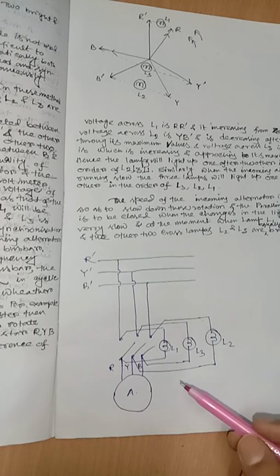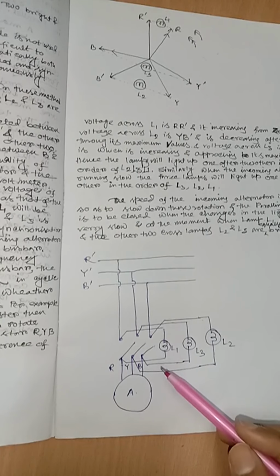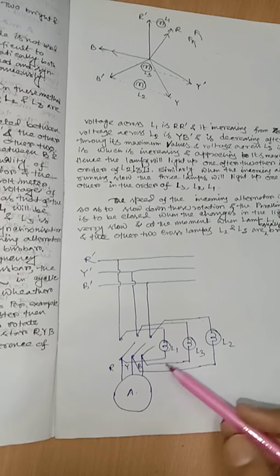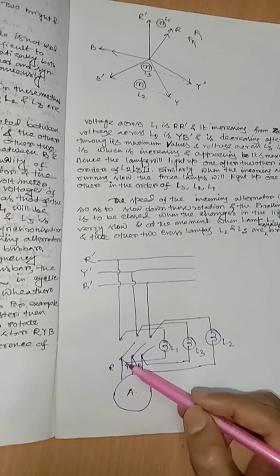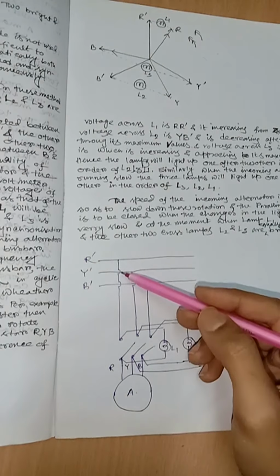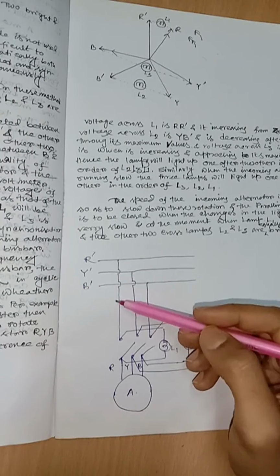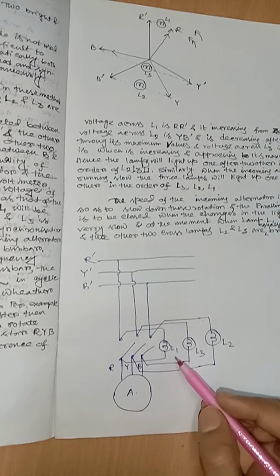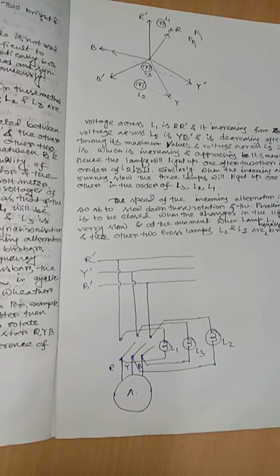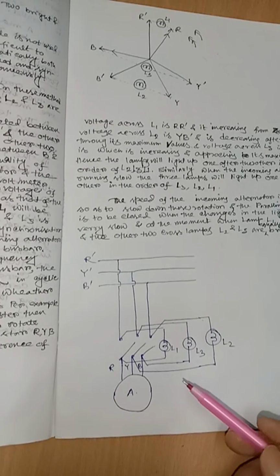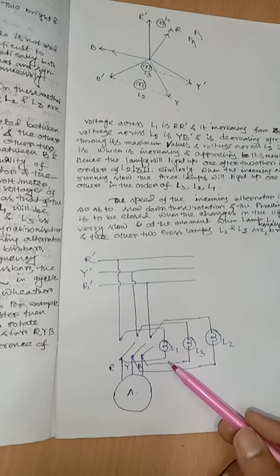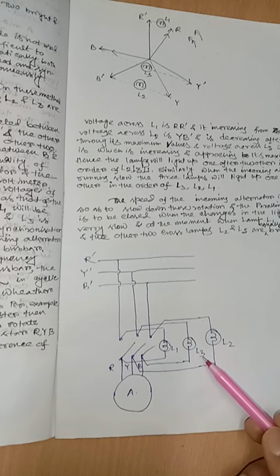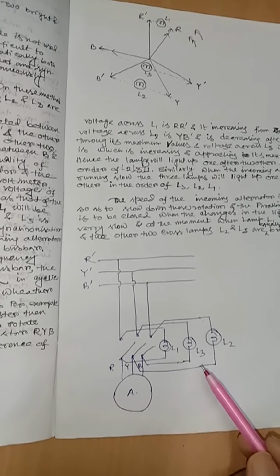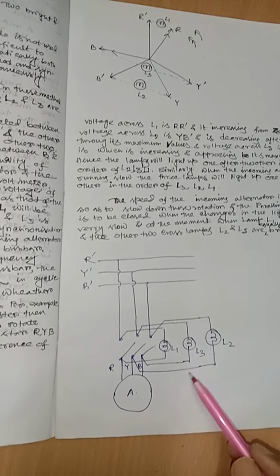In the case of lamp 1, the frequency and phase of the voltage of the incoming alternator are the same, because this is connected in the same phase. The incoming alternator phase is R, and this is the bus bar phase, that is R dash. That is why there is no difference between the frequency and phase of the voltage. So this lamp is dark, and the other two lamps, L2 and L3, are equally bright because they are connected with the corresponding phases.